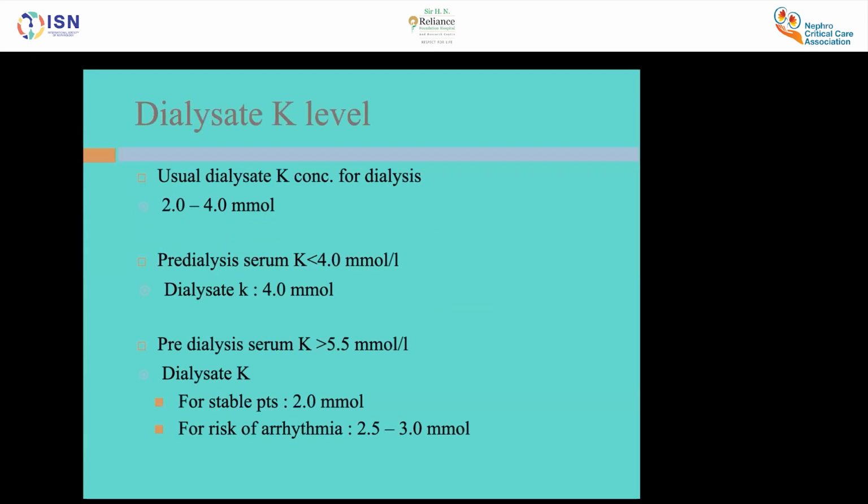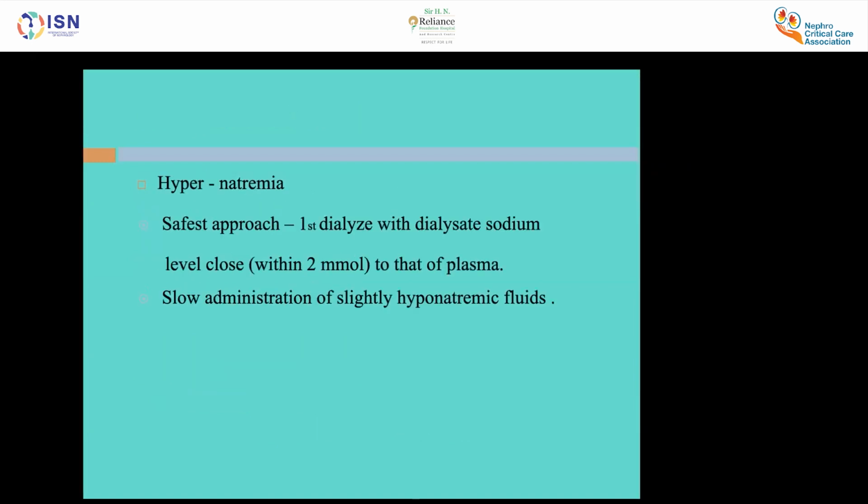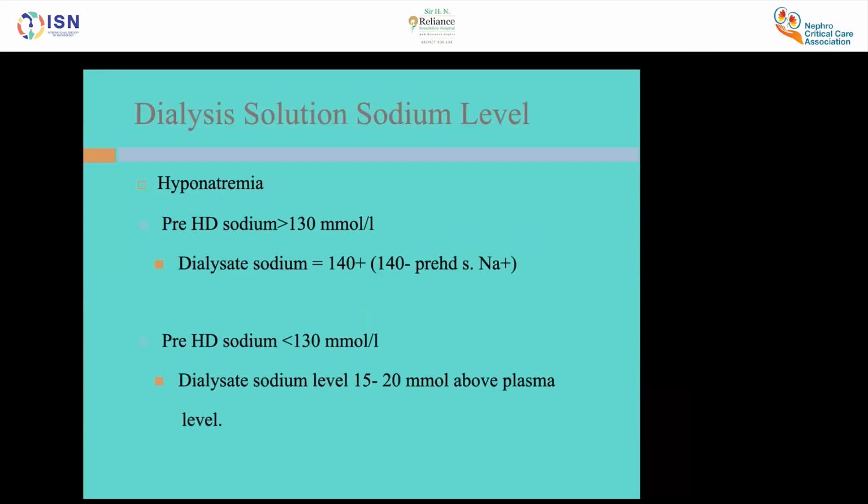Shatarupa and Rushi sir, I have a question on this: how do we manipulate the level of sodium in a dialyzer? This is a very practical question. Last time we were trying to keep the sodium level at 145. I was struggling, and one of the technicians told me, why don't you give sodium separately, directly in the circulation, rather than manipulating through this? It is difficult to increase or decrease the sodium level. Okay.